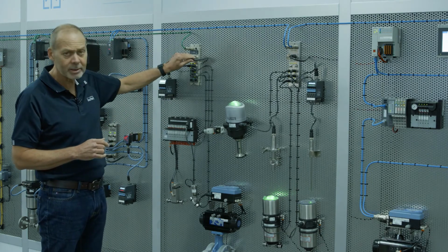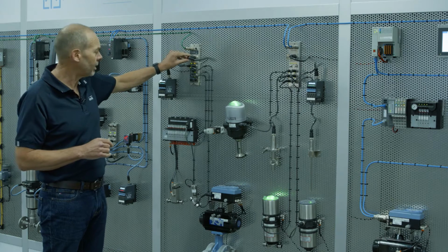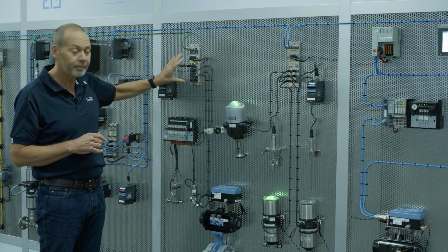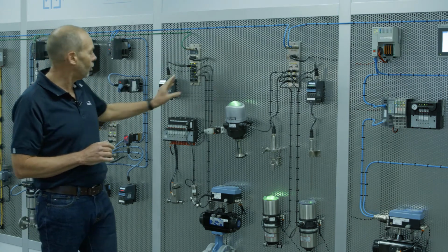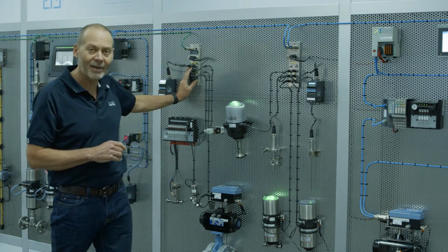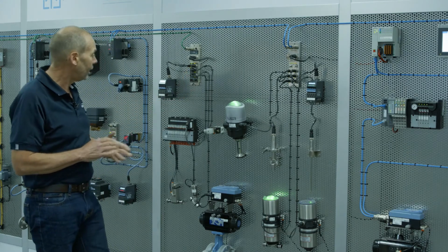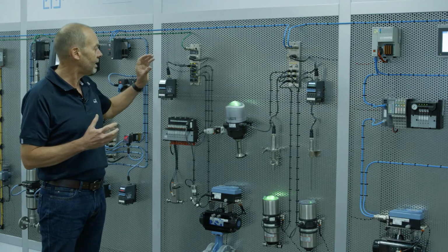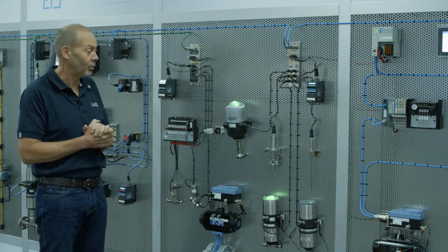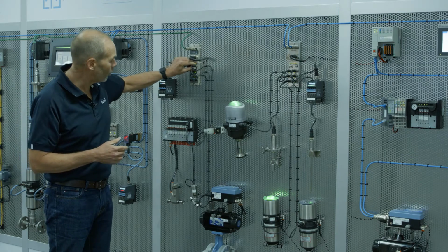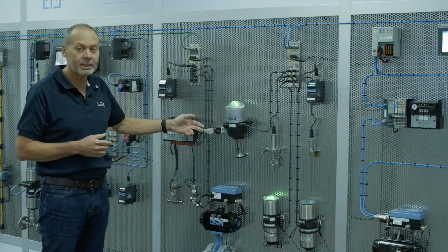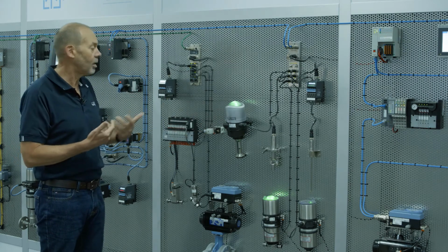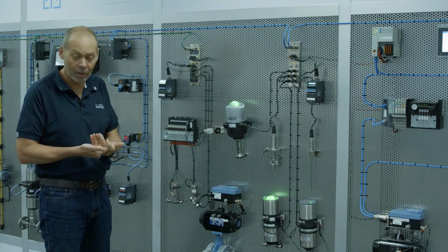You have an additional power supply that can be brought into the modules, so you've got enough power locally to power whatever devices you've got installed. Both of these examples have 8 IO-Link ports. These ports can be set up as just a digital output. This first port is connected just to a solenoid valve in 24 volts DC, so it's operating just as a traditional I/O block.